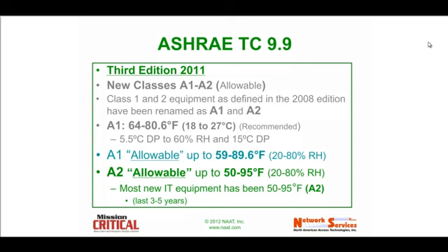The only exception to that area is going to be that of tape. Tape is a little more sensitive, in fact, to humidity changes because of its mechanical nature and sudden changes in temperature. But nonetheless, we've sort of ignored those numbers. We've always lived in that Class 1, now Class A1 recommended range, and people are sort of reticent to do that.